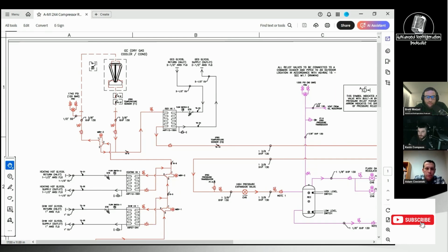I guess one thing to circle back on is the fans and the whole sequence. I think you need to sit down and think about the set points. There's a lot of set points, and they matter for how effectively the system operates. For example, you've got your gas cooler fans minimum set point, let's call it 60 degrees. So the fans are going to regulate to no lower than 60 degrees. Then at some point the fans shut off. They're going to run at a minimum speed, the temperature is still going to drop, then they'll shut off. So you get a little bit of cycling.